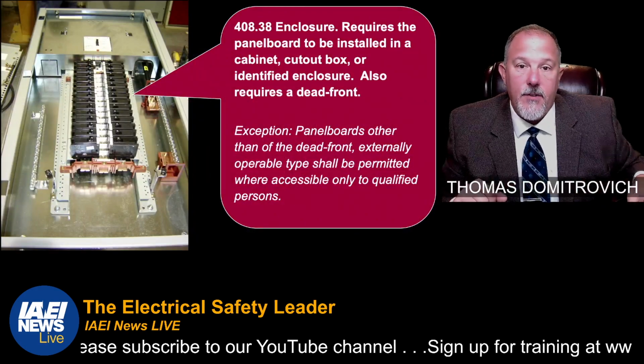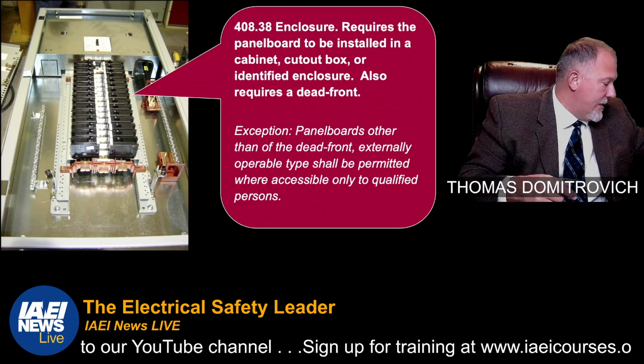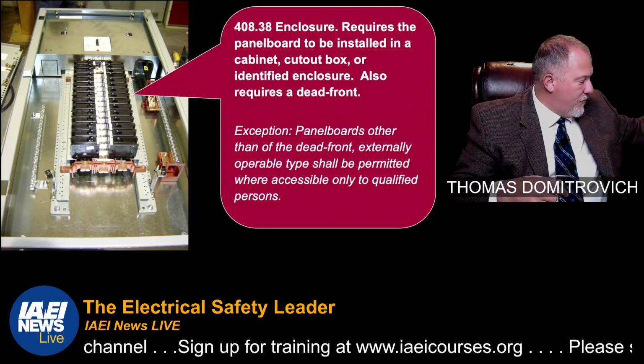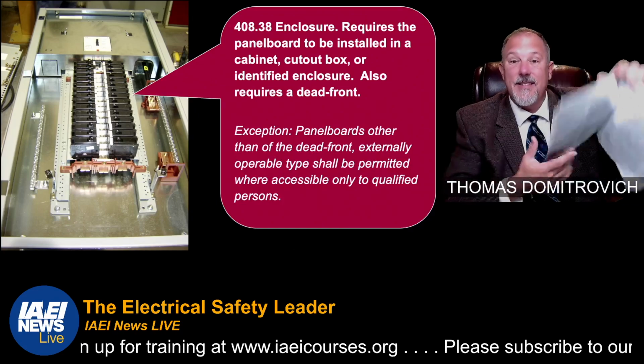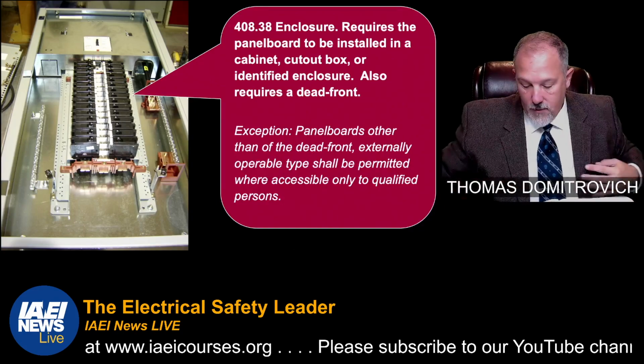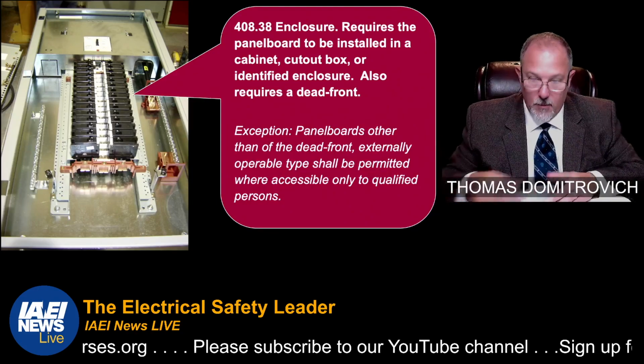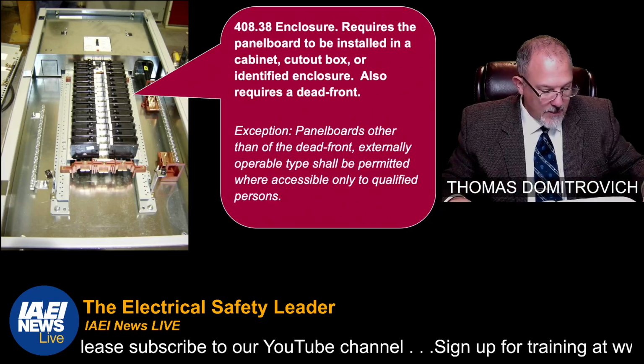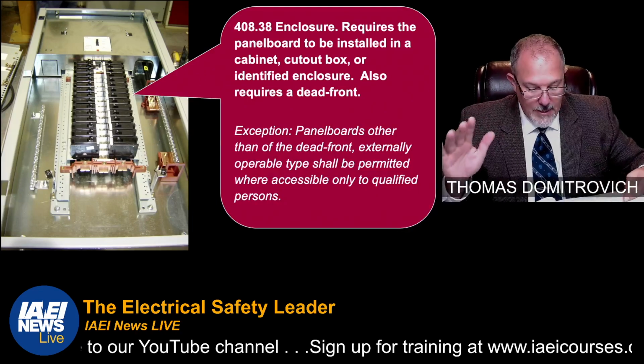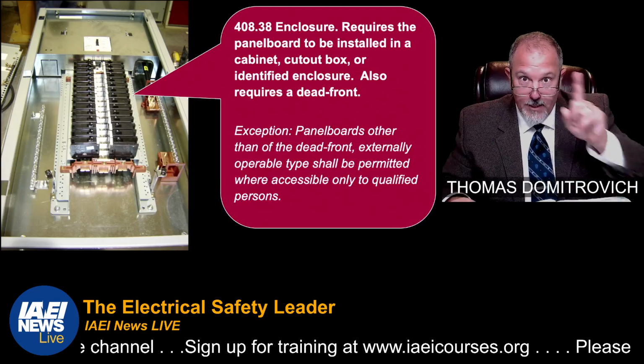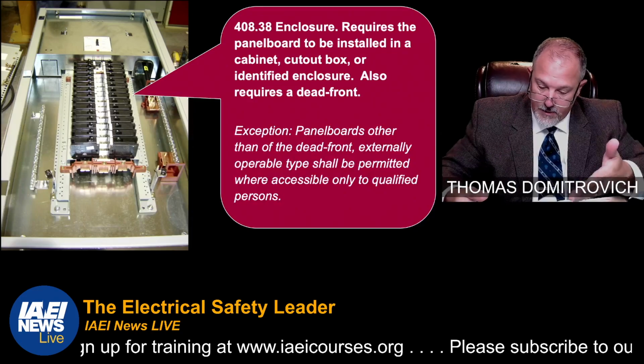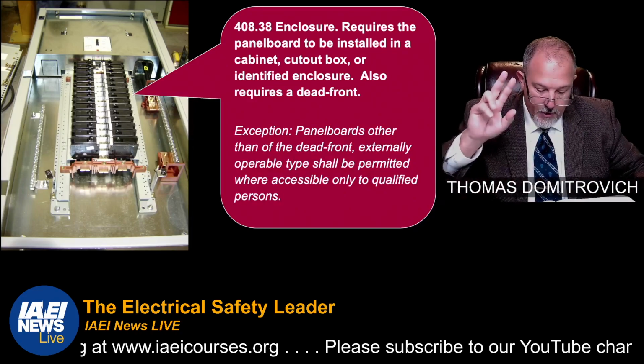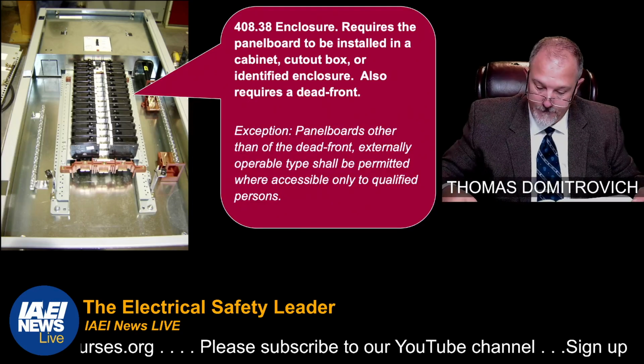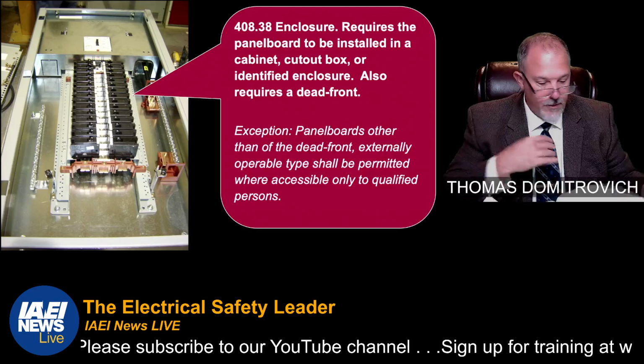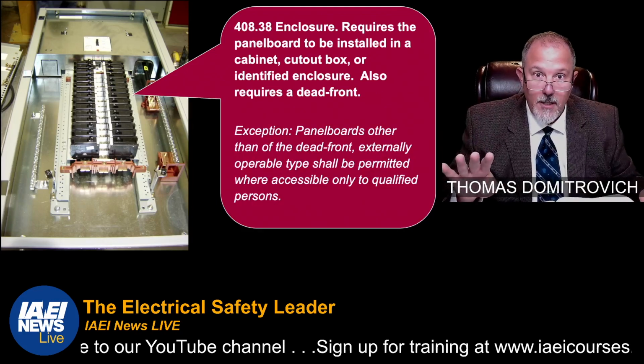there's a difference there. All right, 408.38, it talks about the enclosure. Now remember what the title of 408 is, boy, I'm going to put this book into the Smithsonian. Do you think they'll take it? 408 is switchboards, switchgear, and panelboards. 408.38 talks about, now let's just talk real quickly about how 408 is laid out. You've got part 1 general, that applies to all of these, switchboards, switchgear, and panelboards. Part 2 is switchboards and switchgear only. Part 3, panelboards. Part 4 is construction specifications.